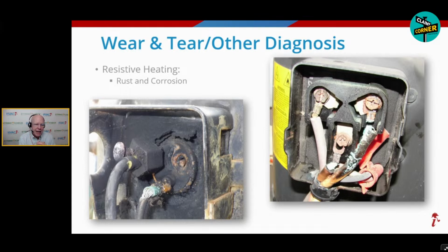The top right one has failed and broke all the way off. We had a little flame event at that time, and it made it all black and charred in there. The bottom wire wasn't far behind it. You see there's rust going on there, and the wire insulation receding, actually melting away from resistive heating. Eventually that one was going to fail as well.